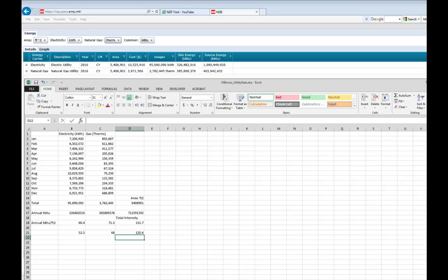We want to look at these numbers and say, are we in the ballpark here? So here's things that we want to look at initially, and we want to talk about. One of the things is that when we look at the difference in our electricity, we know that this is a site number, and this entire site number has other things than just the building contribution to it. And so we have pumping stations, we have sewer lifts, we have things that are outside of the building, street lighting, ball field, athletic field lighting, a lot of different things.